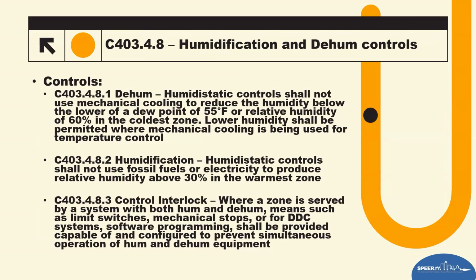And then humidification and dehumidification controls as well. This section prevents waste of energy caused by unnecessary or excessive humidification or dehumidification. So first, dehumidification: the code restricts mechanical cooling from driving humidity down too low. Humidistatic controls can't reduce humidity below a dew point of 55 degrees, or below 55 or 60% relative humidity in cold climate zones, unless cooling is required for temperature control. This prevents overdrying of the space. So once it's at that level, it won't come on and dehumidify.